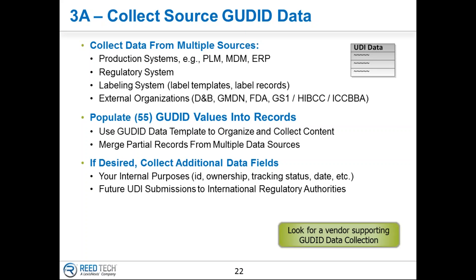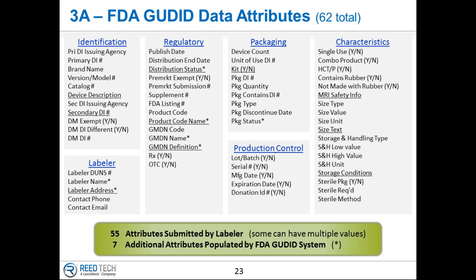There are other considerations as you work your way through collecting this data. The last item talks about collecting additional data fields. I probably would not recommend collecting your international regulatory data at this point in time. For your reference, this slide identifies those 55 fields and the seven additional that the FDA derives from them, for a grand total of 62 in the database.